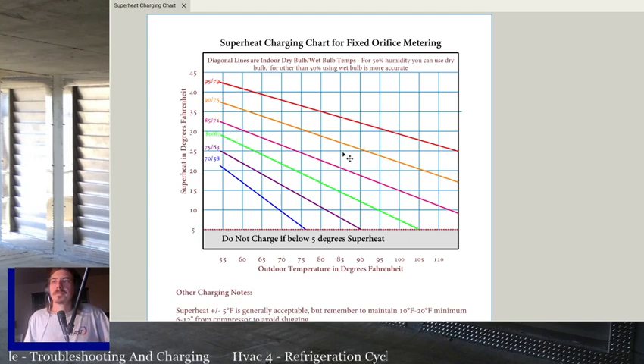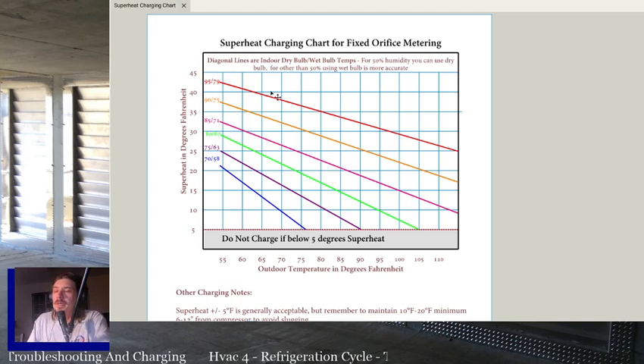But other than that, it's fairly self-explanatory. If we're 80 degrees outside, 75 degrees inside, you're just over 10 degrees of superheat. Basically, you're looking for 10 or 11. So this is just a generic chart. Keep in mind, if you're working on a system, it's always better to use their chart and make sure their orifice is matched and everything's good. But if you don't have their chart, then this is a generic chart that'll get you close enough to make sure everything's working good if you're using a standard fixed orifice.